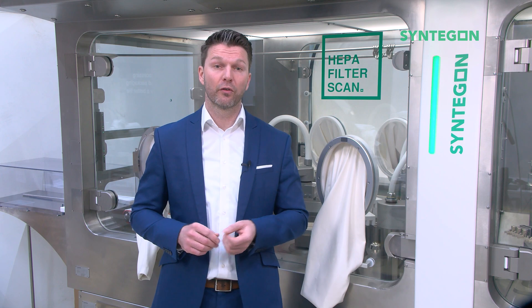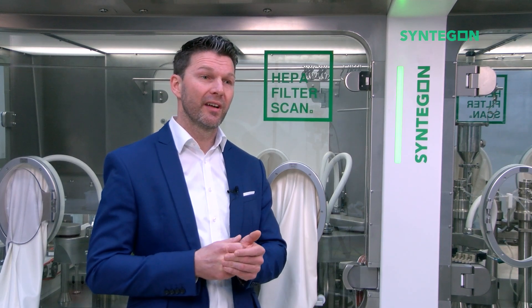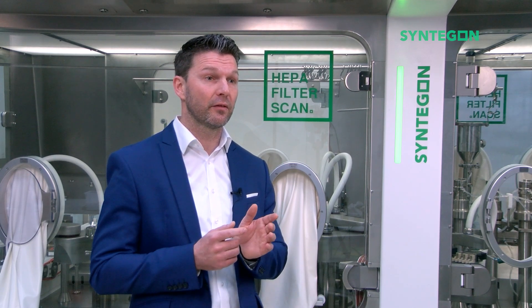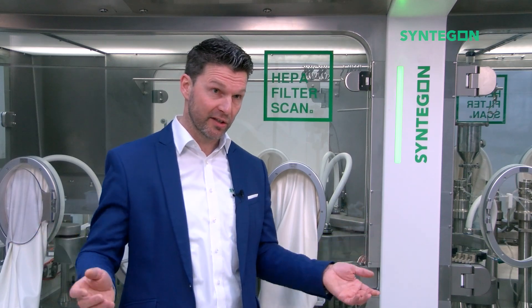With these and other advancements in place, Syntegon isolators are able to achieve the industry's fastest complete cycle time of less than 60 minutes to 1 ppm for a fully loaded commercial scale isolated fill line installed and validated at customer site. Remember, each minute reduced in preparing an isolated filling line increases time for production and contributes to the supply of medicinal products for global health systems.